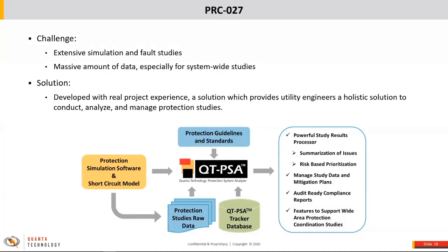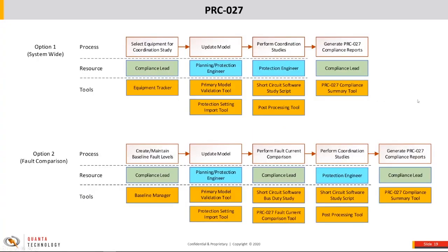Another use case is PRC-27, a compliance requirement coming up later in the year that every utility needs to decide what to do with. One of the most significant challenges is that it requires a lot of simulation and fault studies, which will generate a massive amount of data — especially if you choose a system-wide coordination study. Our solution is an automated tool that connects to the simulation software, applies simulations automatically, generates reports, highlights issues that engineers need to review, integrates protection guidelines that vary by utility, and generates compliance-ready reports.